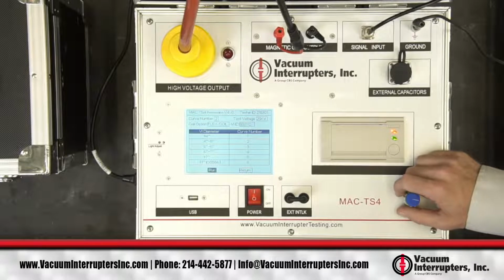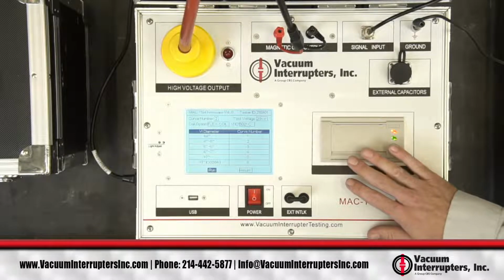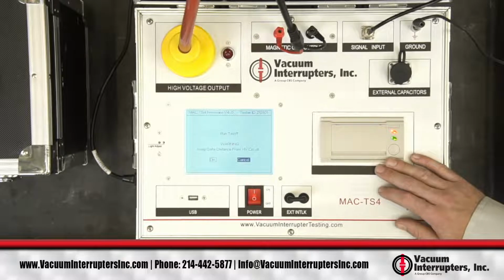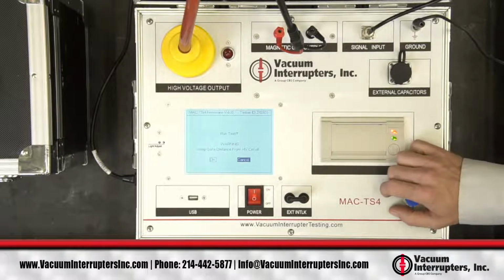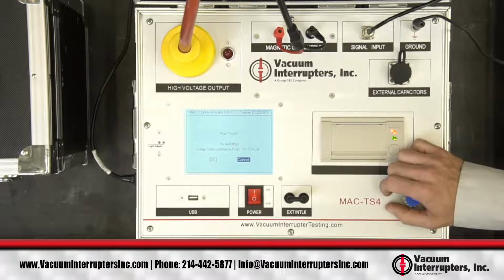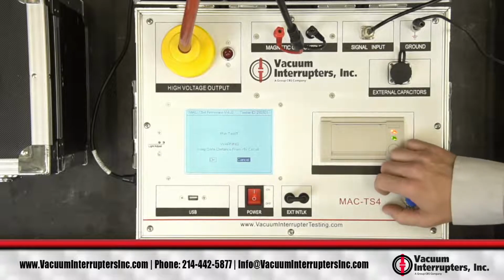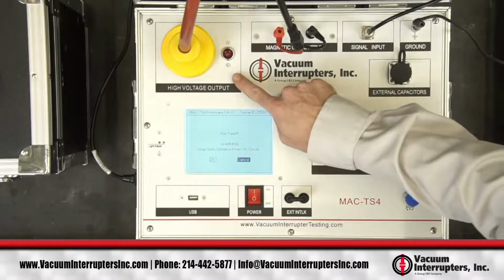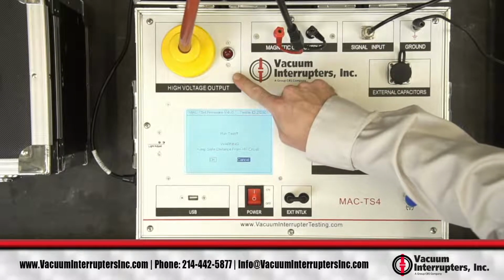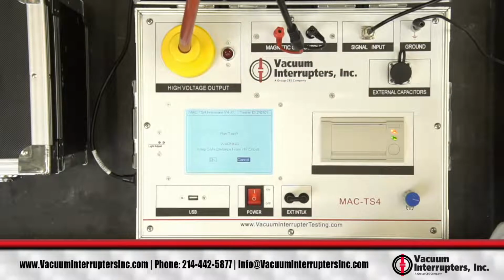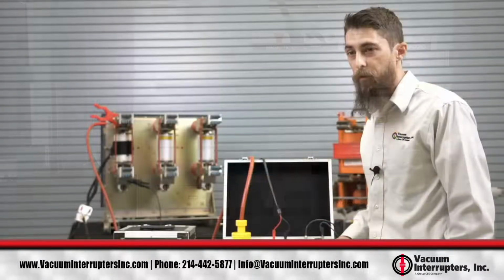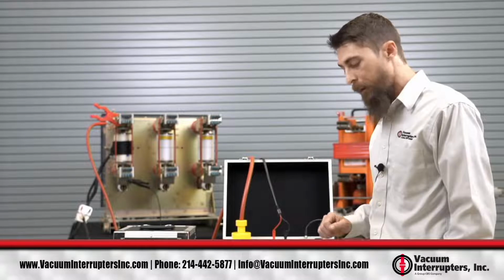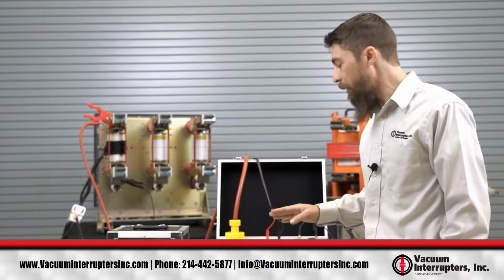So here we're going to go run a test. Before I get started, I'll explain what's going to happen. We're going to first apply high voltage. You'll see a high voltage light come on, and we're going to be measuring the normal leakage current. So there's no magnetic field being applied. It's just like doing a DC high pot.